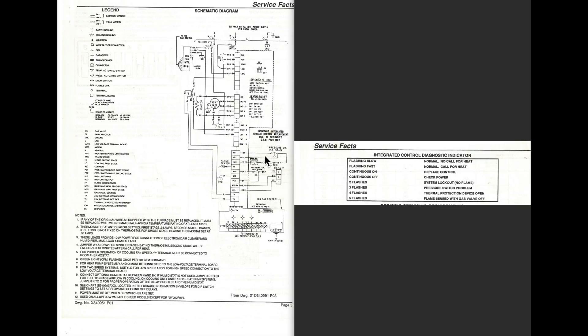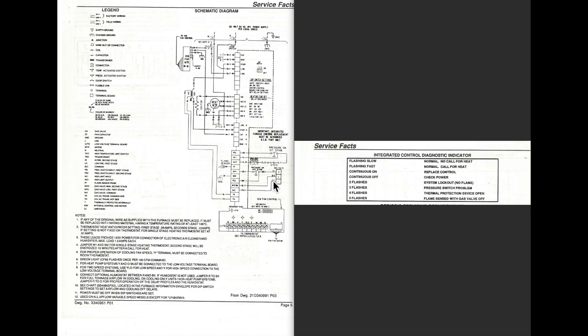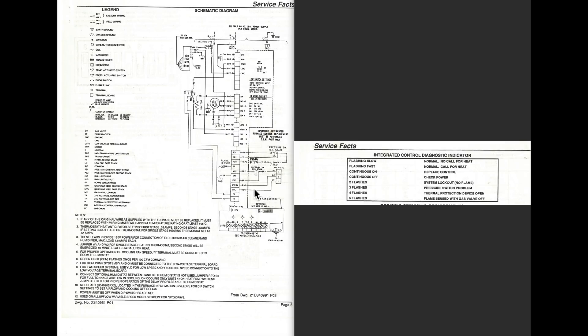At that point, it's going to light up the igniter. Here's the igniter, right there. Igniter is going to warm. There will be a trial for ignition, which means the gas valve down here is going to open. We've got the common right here coming over to the gas valve, and we've got the low fire right here. It's going to turn on the low fire and the gas valve, and if the flame lights, then the flame sensor is going to say okay, we can continue to run. Then there's a time period that starts, and it's about, I think it's 30 seconds, and the ECM fan control goes into the low heat speed, and the fan starts.